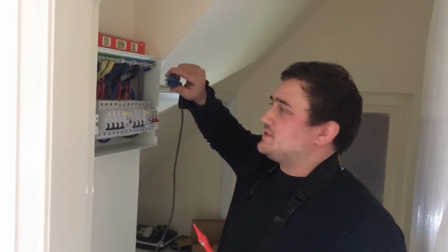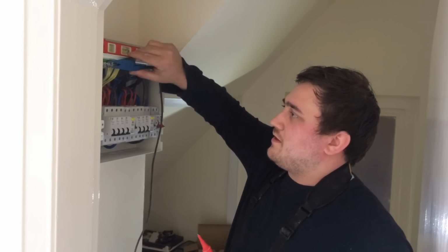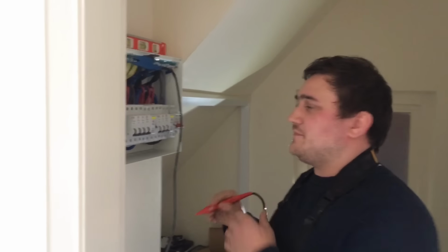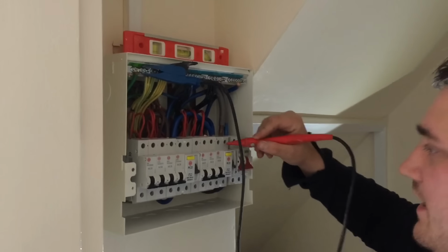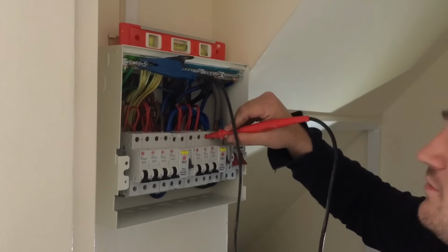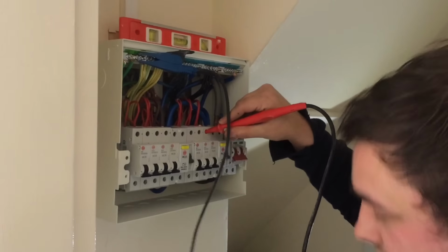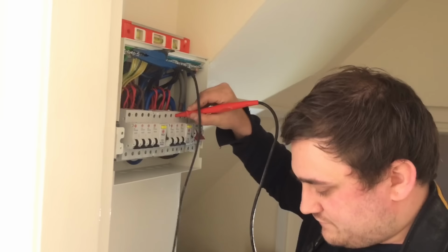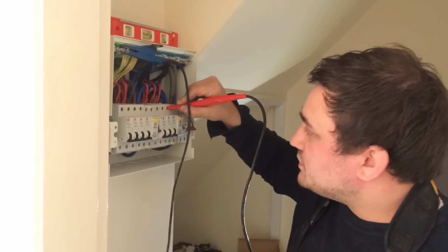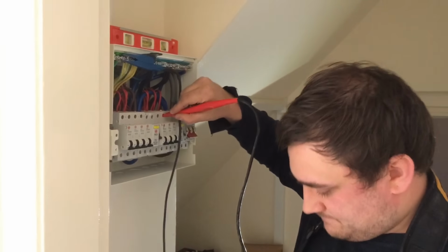Insulation resistance, we're going to go on to the second part, and we're going to do between line and CPC. Same principle. There's only one earth bar here, so we don't have to worry about disconnecting, putting onto a lock, as we did with the neutrals. Again, 500 volts DC, which is going to go across all the top of the breakers.